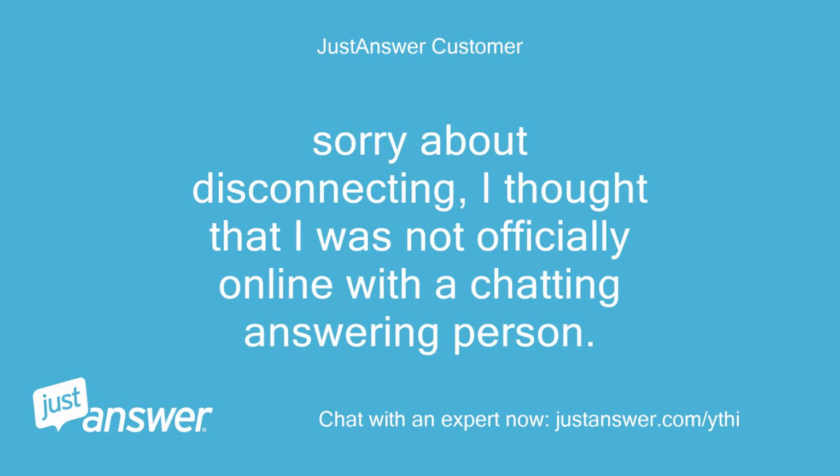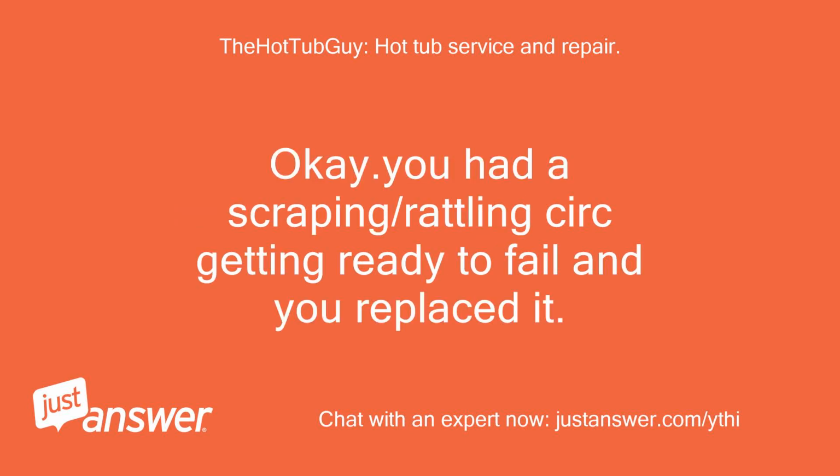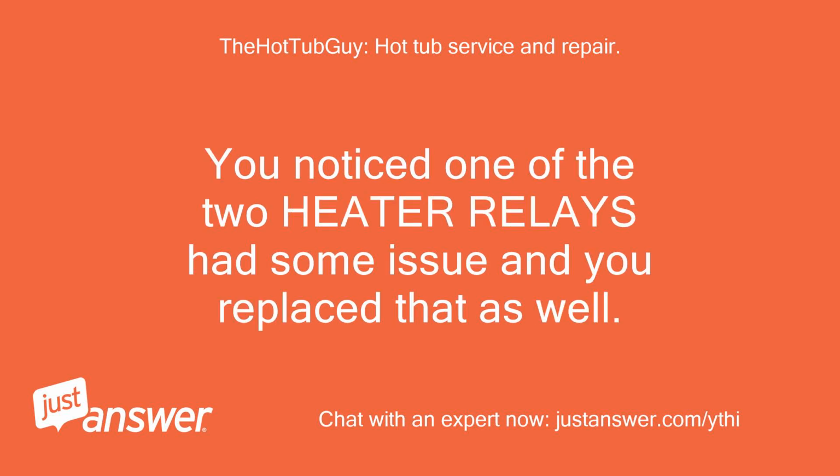Sorry about disconnecting, I thought that I was not officially online with a chat answering person. Hi Steve, no problem. Our posts crossed paths. Okay. You had a scraping/rattling circ getting ready to fail and you replaced it. You noticed one of the two heater relays had some issue and you replaced that as well.